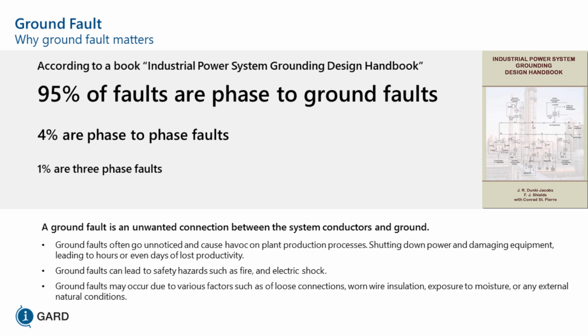You're taking the panel off of a piece of switchgear. It falls onto the three-phase buses. You're causing a three-phase fault. So this is what happens. There are very few times that a three-phase fault is going to occur. And IEEE 1584 states that you have to consider all faults as three-phase faults to calculate the incident energy. Well, it occurs less than 1% of the time.